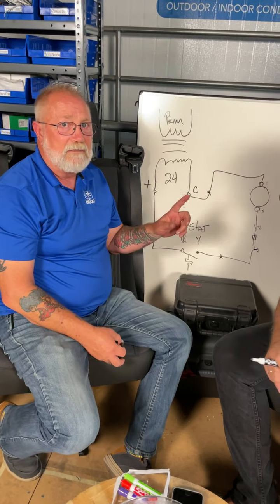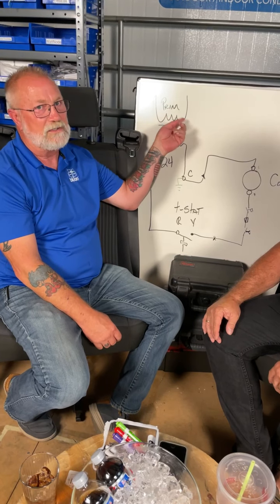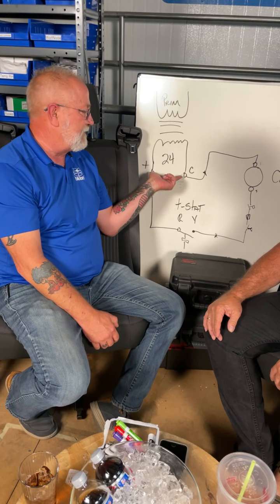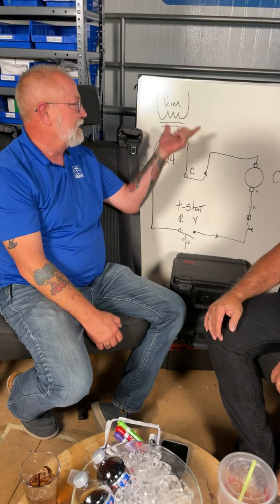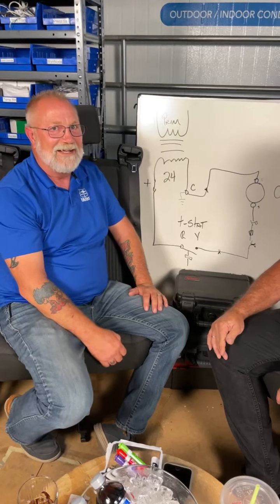Get a bigger transformer. No, just kidding. That's where you go up, Mikey calls it the prim. That's where you go to your primary side and see if you've got primary voltage. And again, I didn't write it down. It's either 120 or 230, or if you get into the larger equipment, it could be 460 as your primary voltage side. So always be careful, know what you're working with. But if you don't have it at the transformer, check your primary, make sure that your primary has power, and then call Mike. Couple more questions from Brianne.